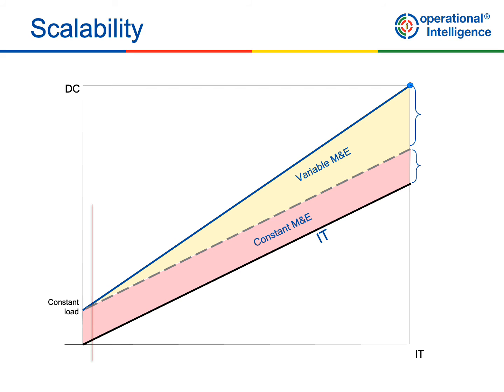In this case, you can see that at 100% load, our ratio for the IT load with the total data centre load is approximately 1.5. But down at day 1, where we first start putting IT equipment in the data centre, the ratio is much worse. It's around 10. So if we're designing things and optimising them for operations, and we're able to reduce our constant M&E loads, so the mechanical and electrical overheads, we can see an improved performance at low load and throughout the data centre's facility lifespan.